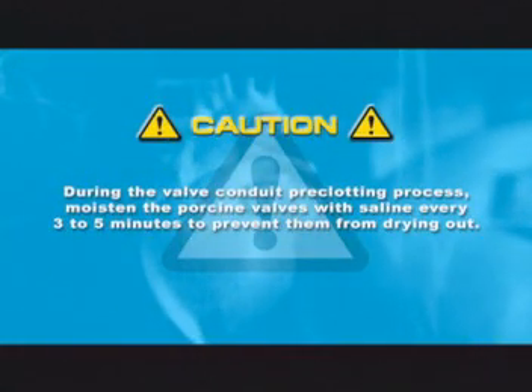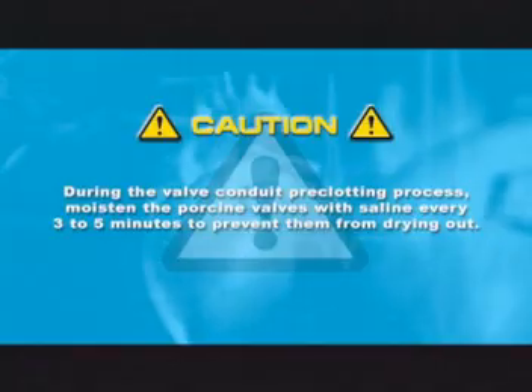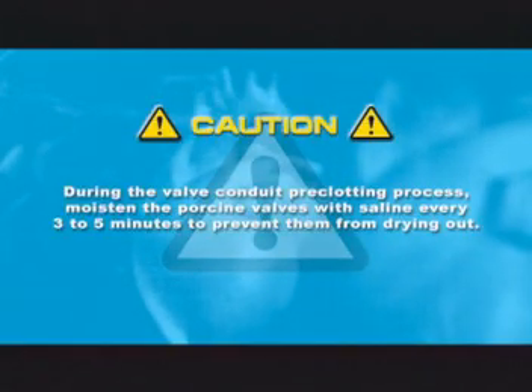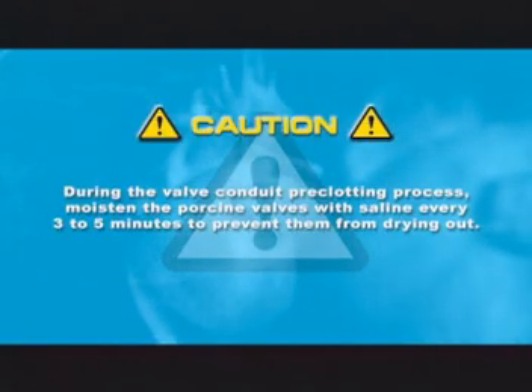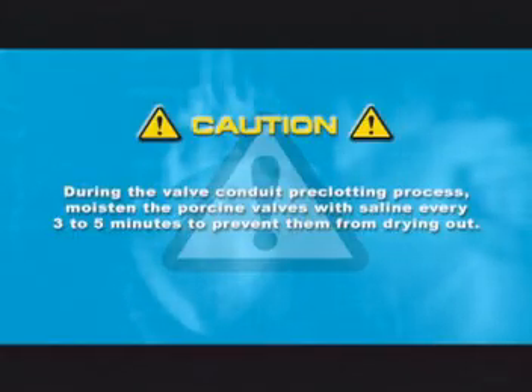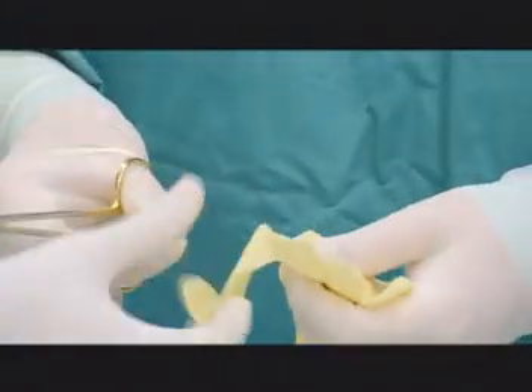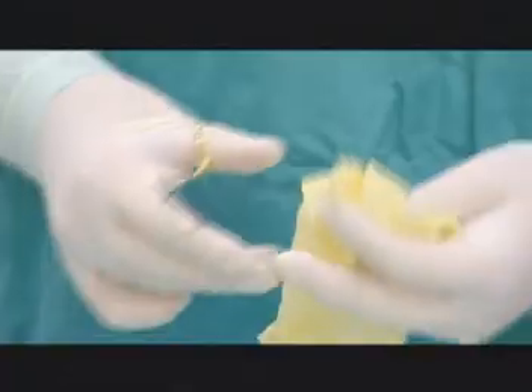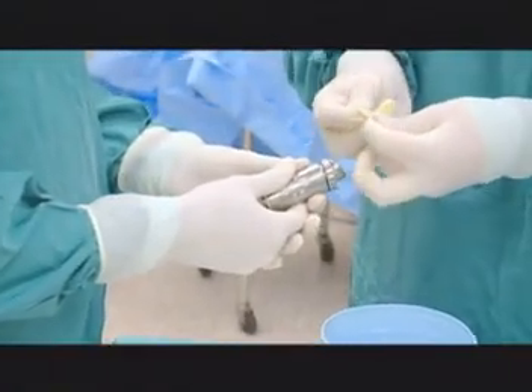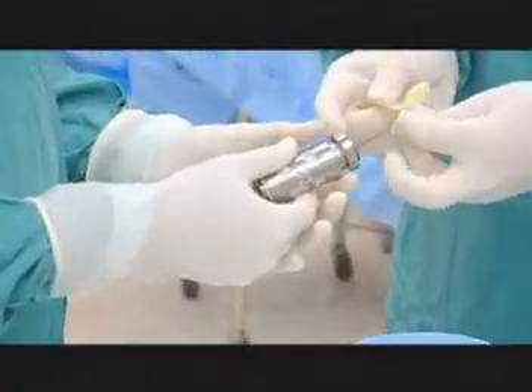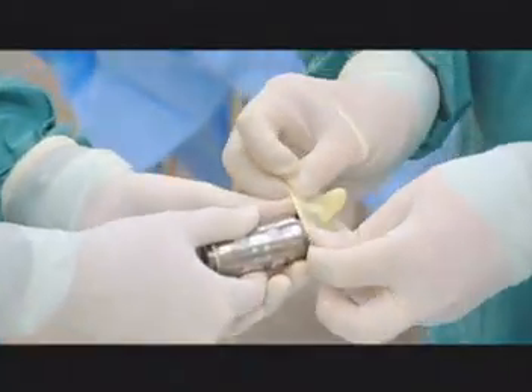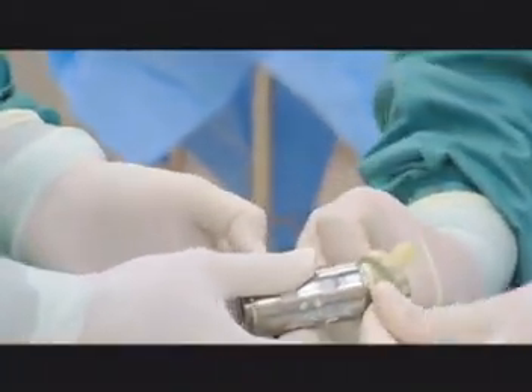Caution: during the valve conduit pre-clotting process, moisten the porcine valves with saline every 3 to 5 minutes to prevent them from drying out. To prevent the pre-clotting agent from contacting the tissue valves inside the valve conduits and to protect the valve threads, place finger cots cut from sterile, non-powdered glove tips onto the ends of the valve conduits.